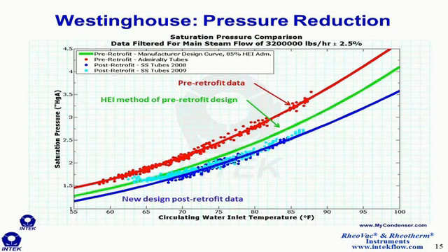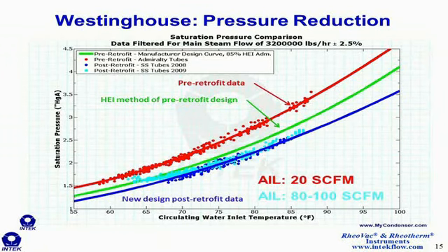So again, the pre-retrofit data is shown in red for the clean condenser prior to the retrofit. And then the retrofit was installed, and there's 2 years of data after the retrofit shown in blue and teal. You can see a 1-inch pressure decrease from the pre-retrofit condition. And one thing to note is that in the pre-retrofit condition, all of that data is with the condenser operating with 20 SCFM of air in leakage.